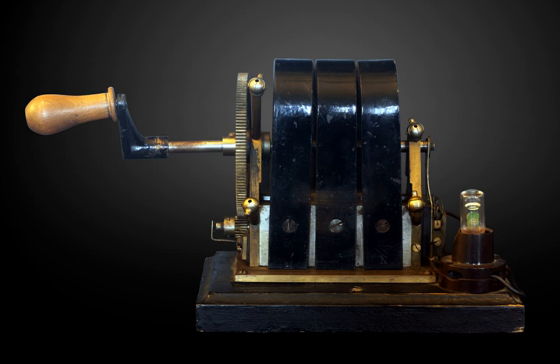The shunt wiring of the generator feeds some of its output current back into the field coils, which in turn increases output. By this means, the field builds up regeneratively, though this may take 20 to 30 seconds to do so fully. Use of magnetos here is now obsolete, though separate exciters are still used for high-power generating sets, as they permit easier control of output power. These are particularly common with the transmissions of diesel-electric locomotives.